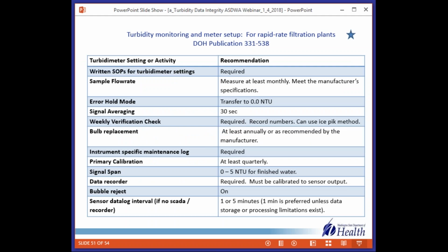I think it would be good to just talk about what we think are the highest priority settings to be looking at. So the first one is kind of obvious, but yes, you need a data recorder, and it needs to be calibrated to the output of the controller. Signal span, we think that 0 to 5 NTU for finished water is a good balance between not capping and data resolution, and from what outputs we would expect.